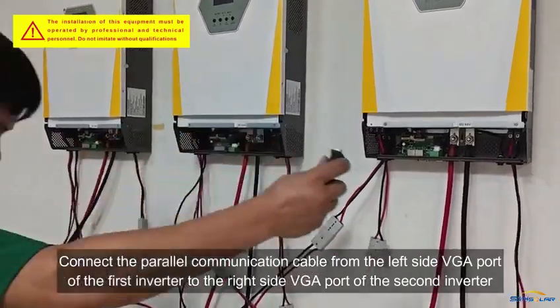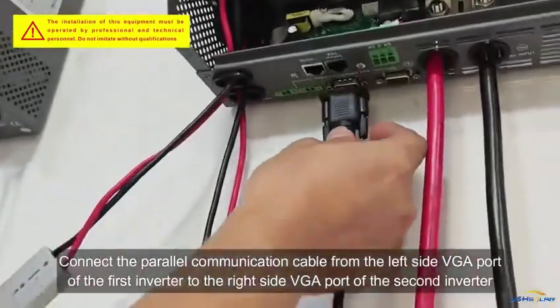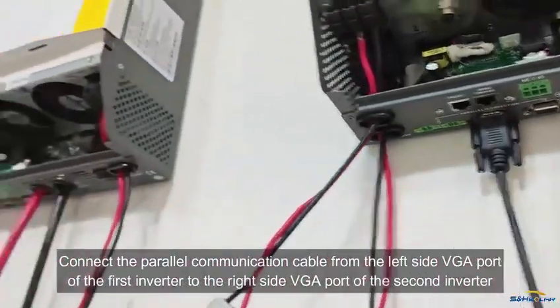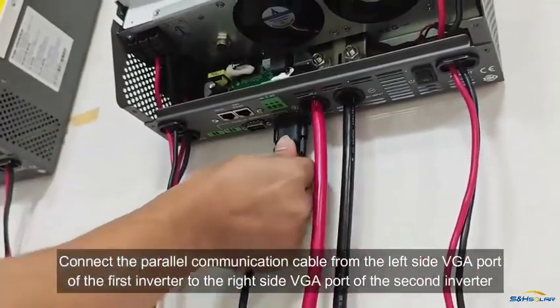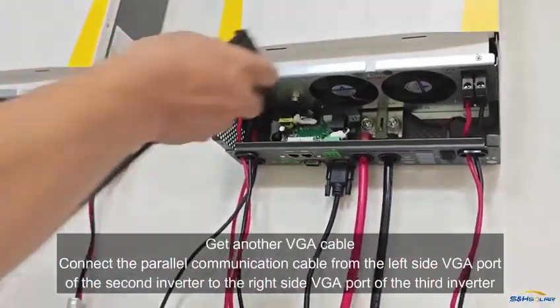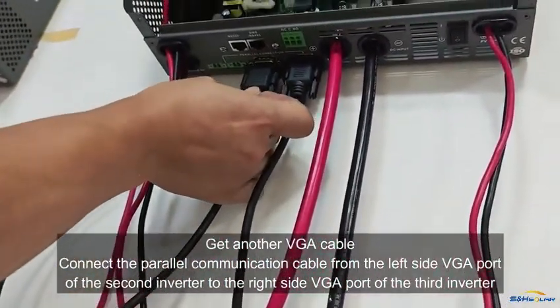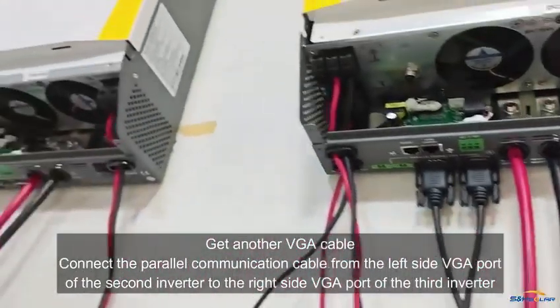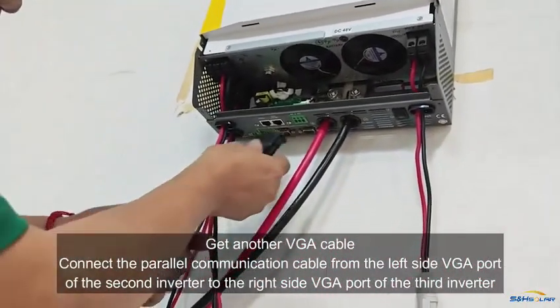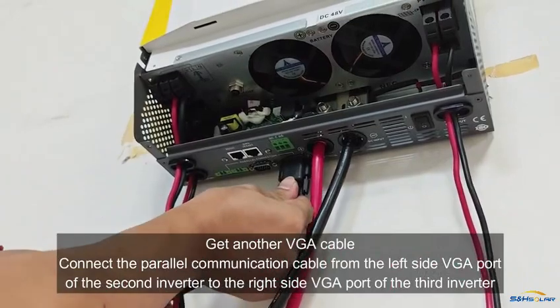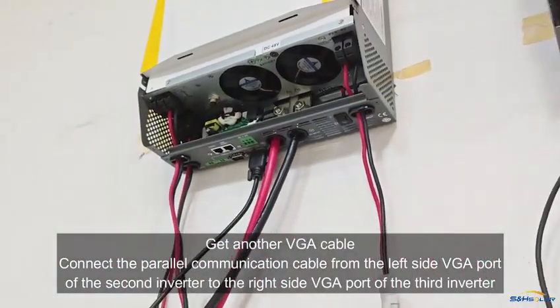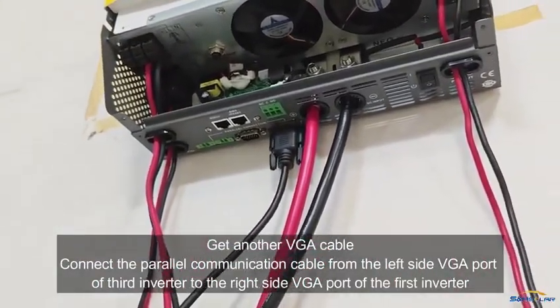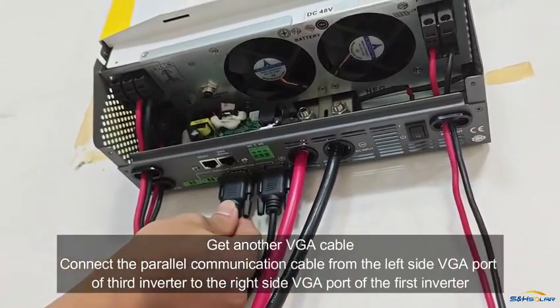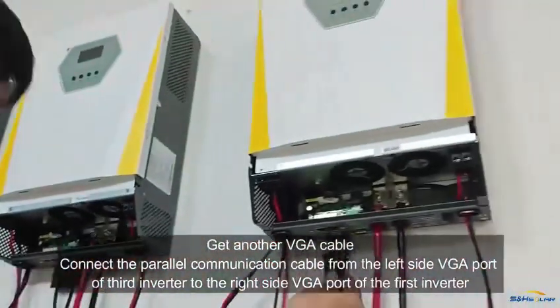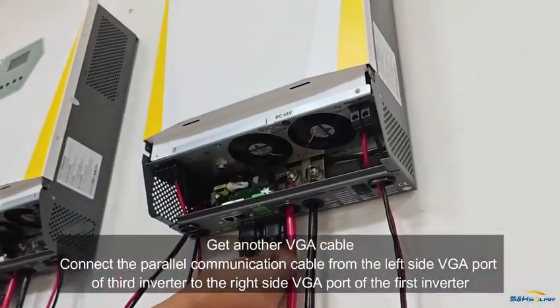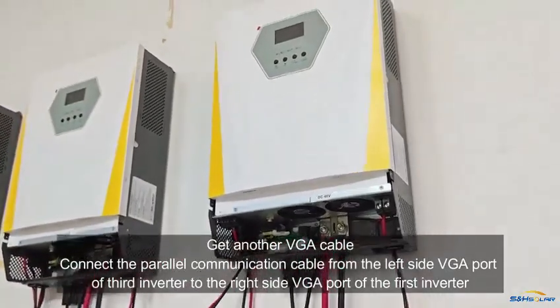Connect the parallel communication cable from the left side VGA port of the first inverter to the right side VGA port of the second inverter. Get another VGA cable. Connect the parallel communication cable from the left side VGA port of the second inverter to the right side VGA port of the third inverter. Get another VGA cable. Connect the parallel communication cable from the left side VGA port of the third inverter to the right side VGA port of the first inverter.